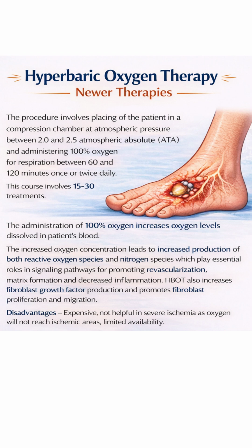The procedure involves placing the patient in a compression chamber at atmospheric pressure between 2 and 2.5 atmospheres absolute and administering 100% oxygen for respiration between 60 and 120 minutes once or twice daily.